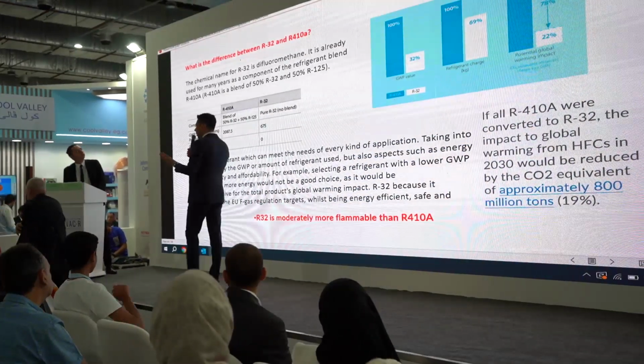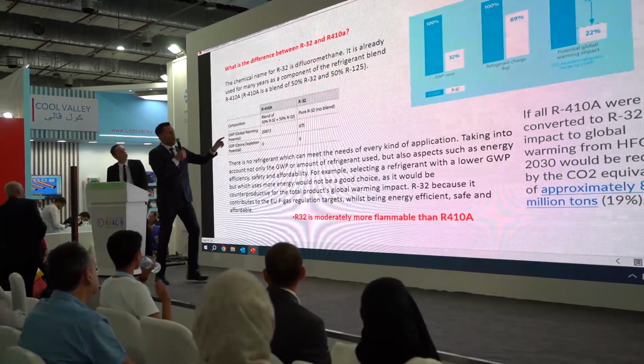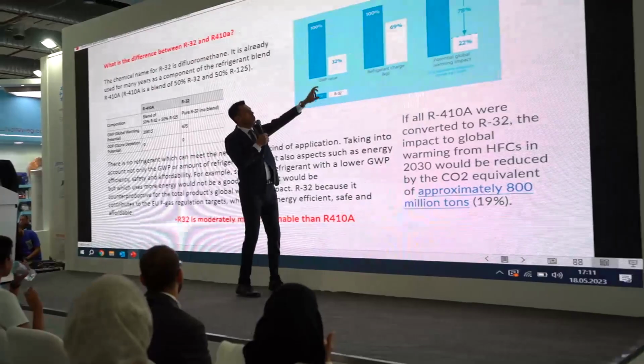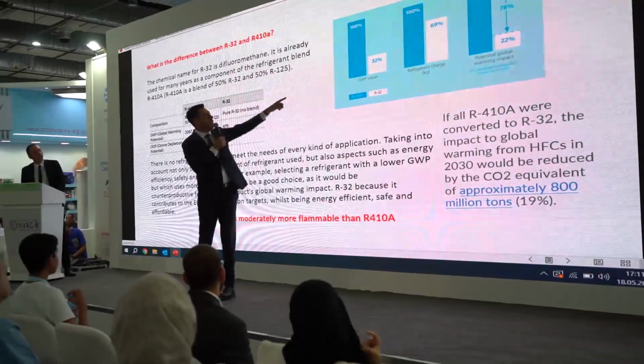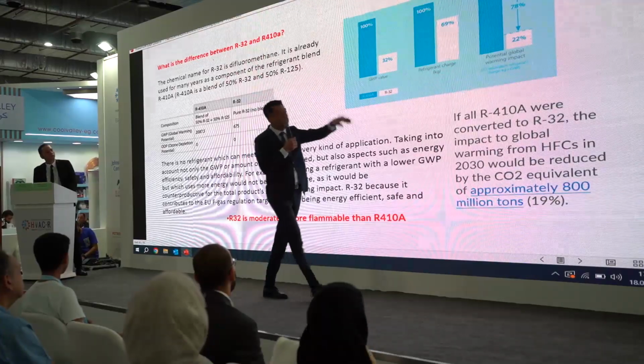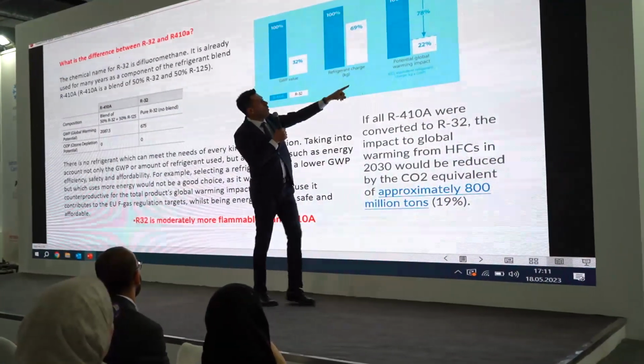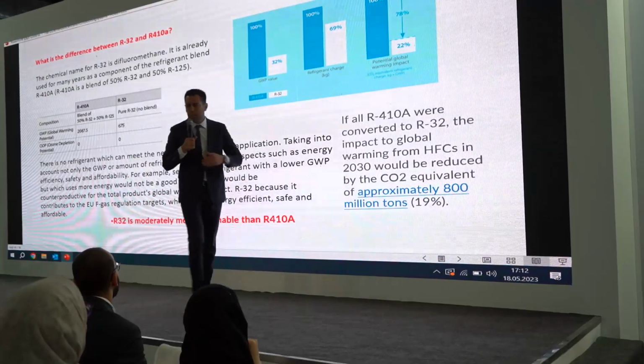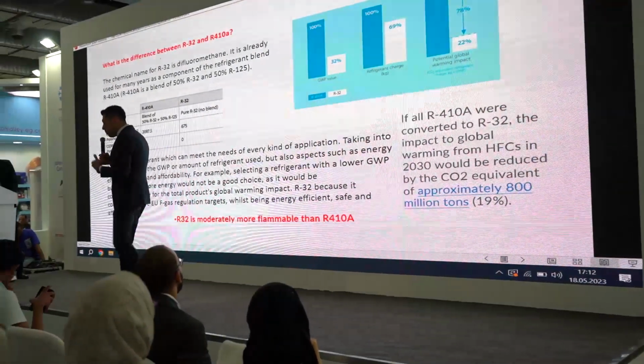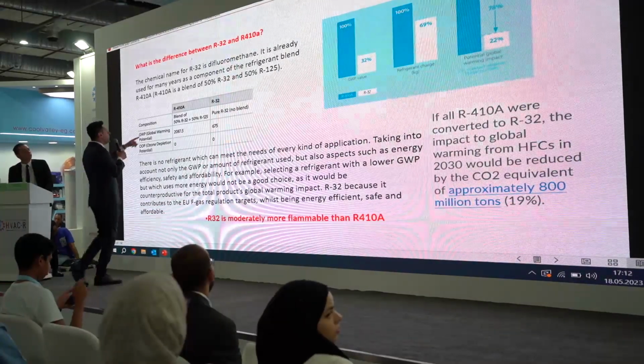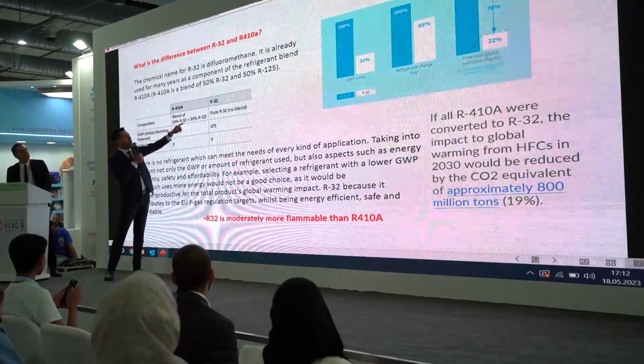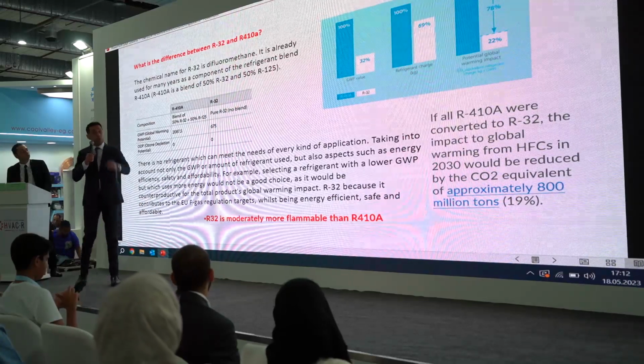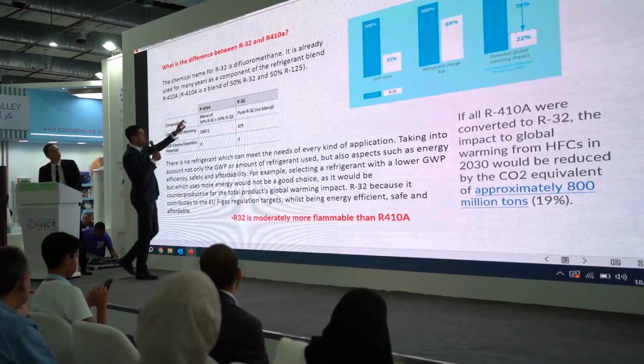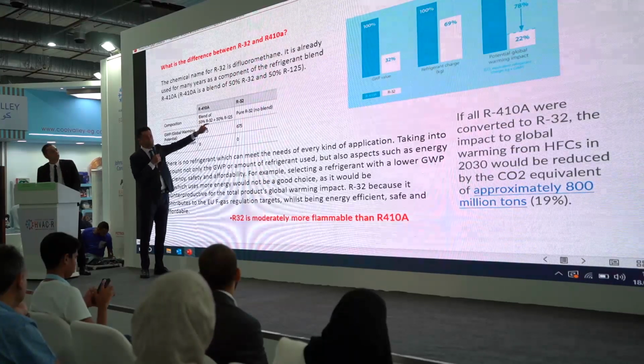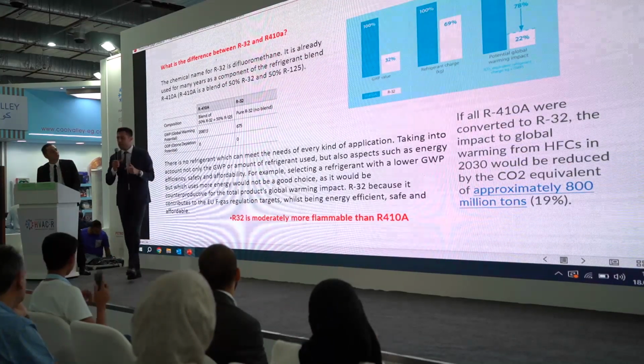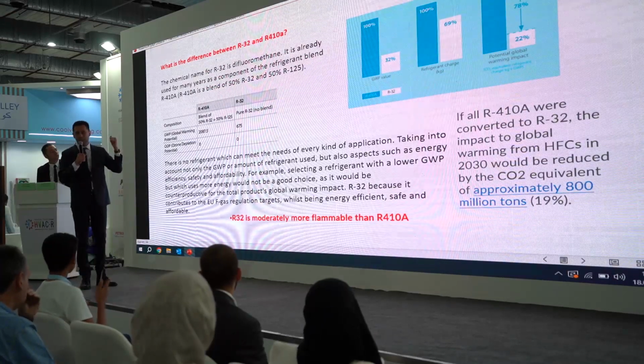Here is a good question for you. As you see, R32 has lower global warming potential than R410. Refrigerant charge is less, and the potential global warming impact is less, so it's more efficient and less impactful to the environment. But the problem is R410 is a blend of R32 and R125. Meaning that at the time they started using 410, R32 was already invented. So why didn't people use R32 from day one?